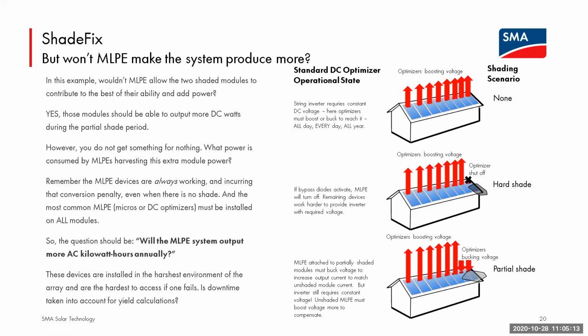What SMA, on the contrary, is providing you is a much simpler device on the roof. So it's a purely rapid shutdown device. It's allowing current to pass through normally. So it's not generating any heat. It's not giving you an efficiency hit like the rival products are. And the inverter is still able to deal with non-shade, hard shade, and partial shade.